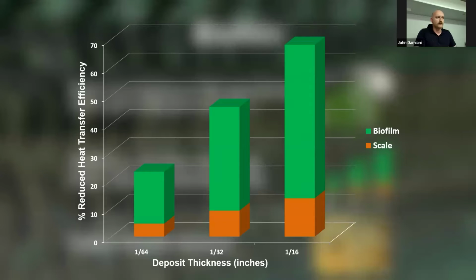I've got this on a stacked bar because often you see them in combination. When there's big problems in the system, you often see scale and biofilm simultaneously. But if you separated them out, you'd see that, for example, a 1/32 of an inch deposit thickness for scale will get you close to a 10% loss in your heat transfer efficiency. Well, 4 times that, almost another 40%, would be on top of that for the biofilm. So it really causes a major problem.